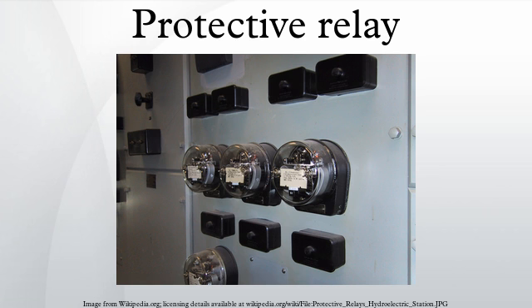The relay's primary winding is supplied from the power system's current transformer via a plug bridge, which is called the plug setting multiplier. Usually 7 equally spaced tappings or operating bands determine the relay's sensitivity. The primary winding is located on the upper electromagnet. The secondary winding has connections on the upper electromagnet that are energized from the primary winding and connected to the lower electromagnet. Once the upper and lower electromagnets are energized, they produce eddy currents that are induced onto the metal disk and flow through the flux paths.